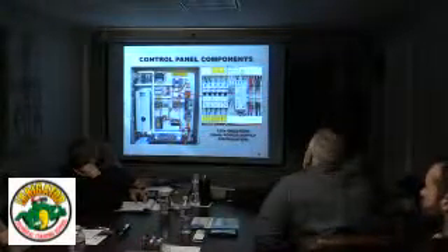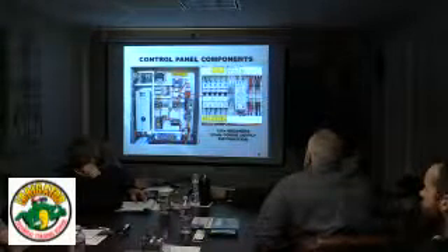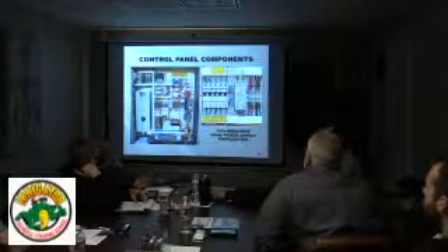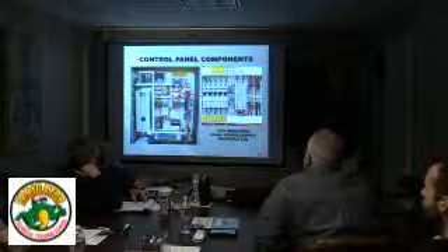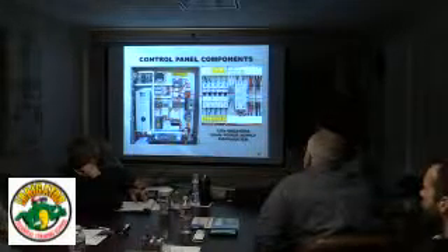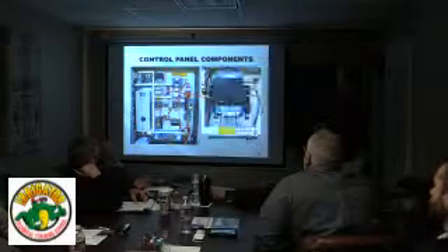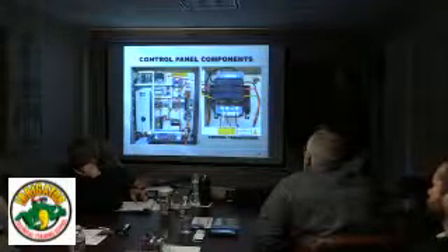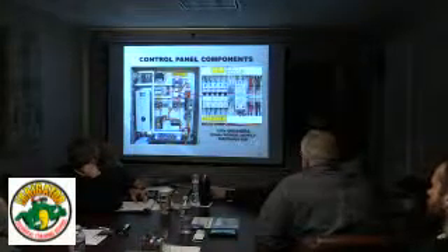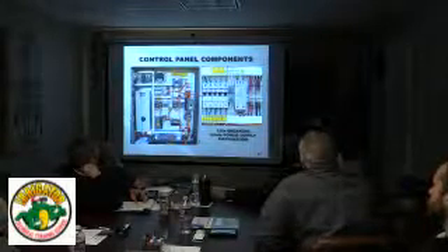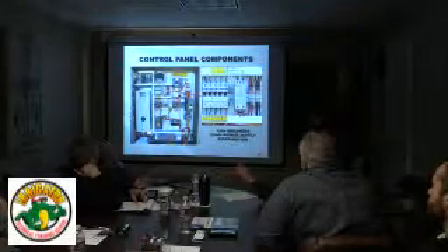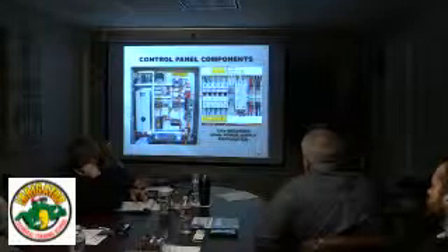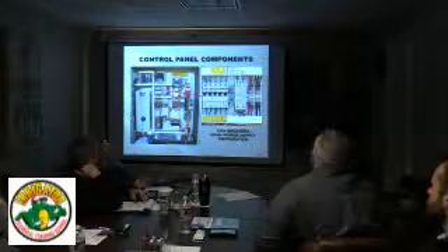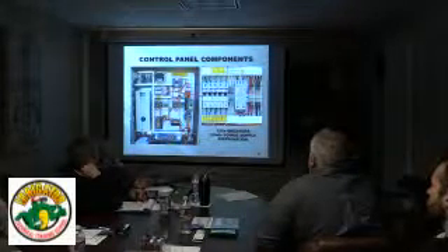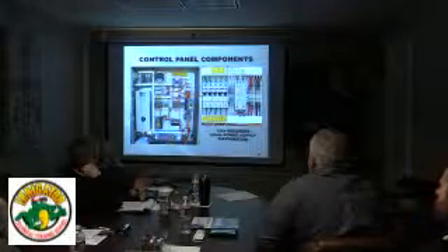Here's our breakers. Most of our systems will have a set of breakers in them, maybe 1, 4, or 5. Again, on the control transformer, we've got our 120 hot right here. It jumps down and goes straight into the top of this one. You'll notice there's 2 wires here. We just simply jump across over this one, to this one, and to this one. And that way our control transformer 120 volt is at the top of all these breakers, and then each one of these breakers will go out to a different circuit.